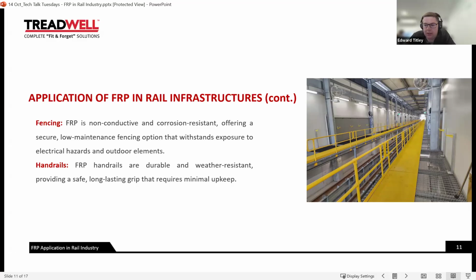You'll also see the yellow strip, a product we supplied for two main reasons. In hindsight, FRP grating would have been a good solution, but the steel grating was already installed. So we applied this 3mm thick top plate to do two things: stop dropped objects going through the steel grating, and prevent any issue with the body of the train being earthed out into the platform via a torque wrench or large spanner, which was a concern. That fixes those two issues.